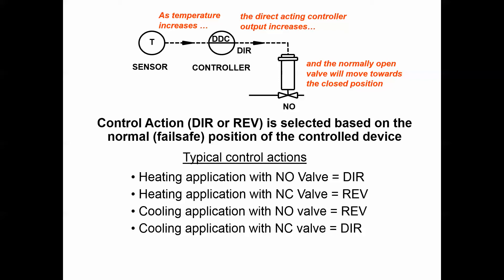With a heating valve, if you want it to fail normally open, you would select a direct acting control output so that as you start increasing the output as the temperature starts rising, you're going to be getting away from that normally open position.